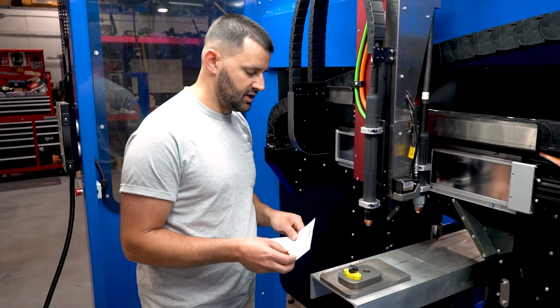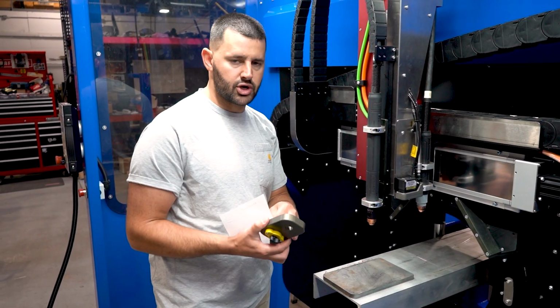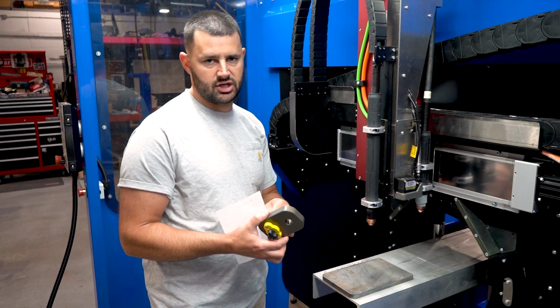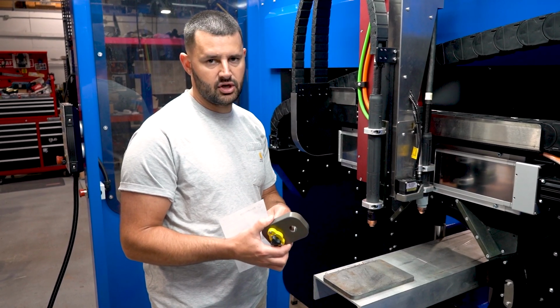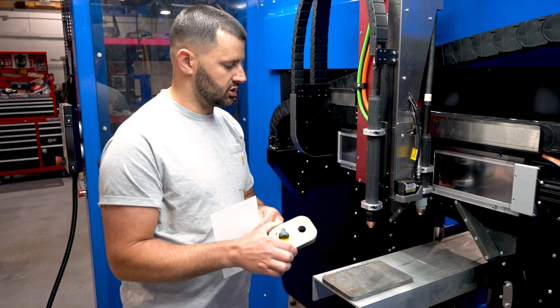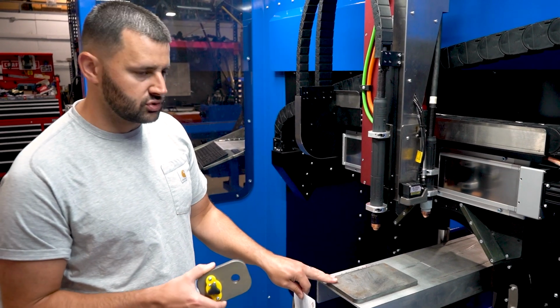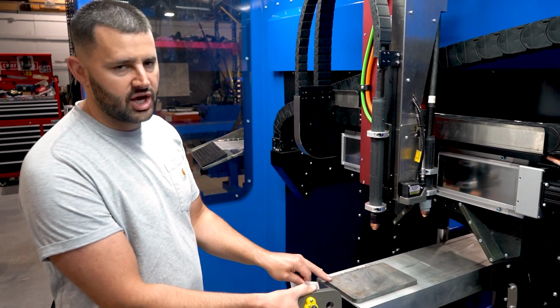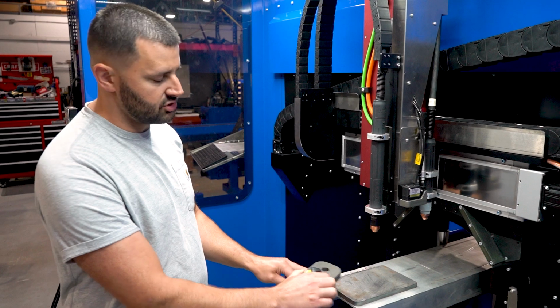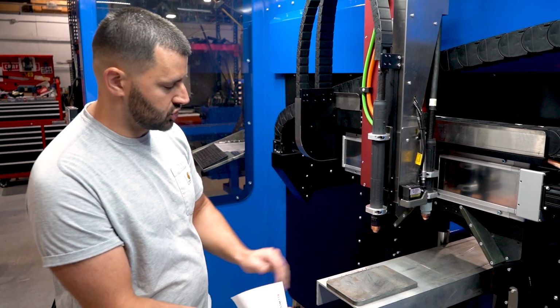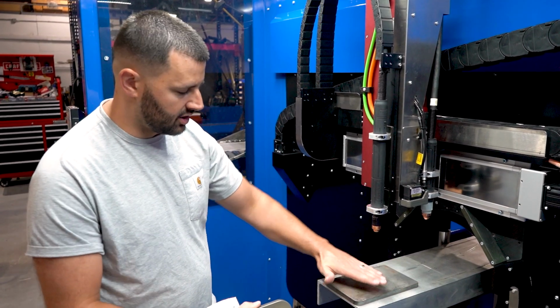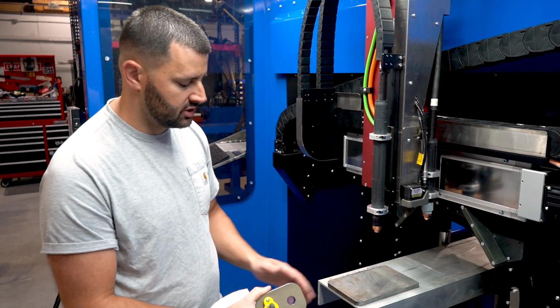What you're going to need is, this is the calibration block. This comes with the machine. It could be located in your cabinet or on one of the arms of your monitor station. This is a special piece of aluminum channel we use internally, but you can just get a standard piece of 8-inch C channel. Make sure it's relatively flat. It doesn't have a crown in the top of the C channel.